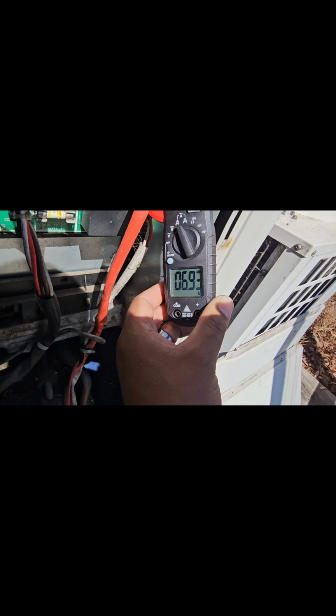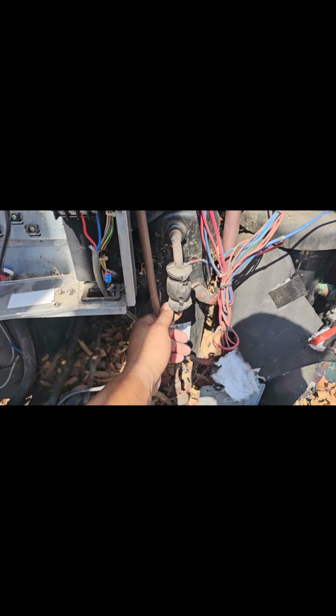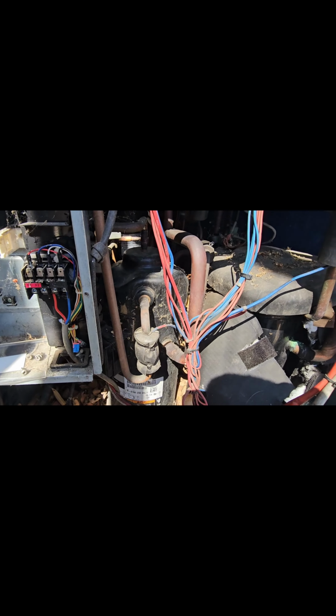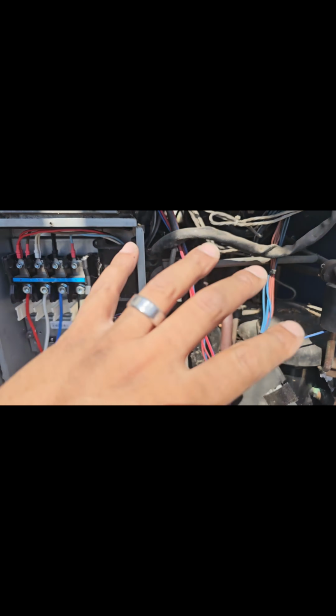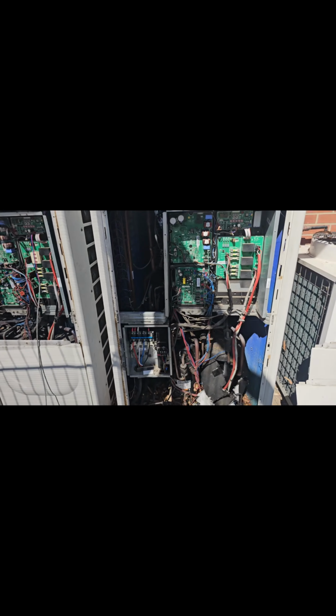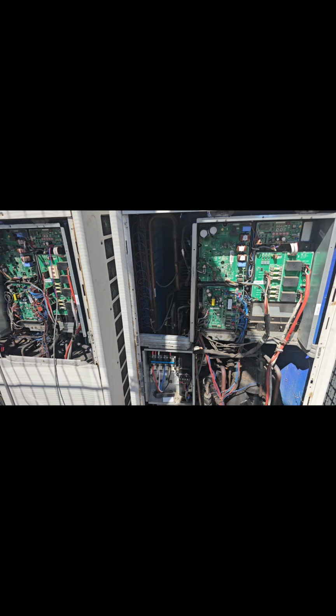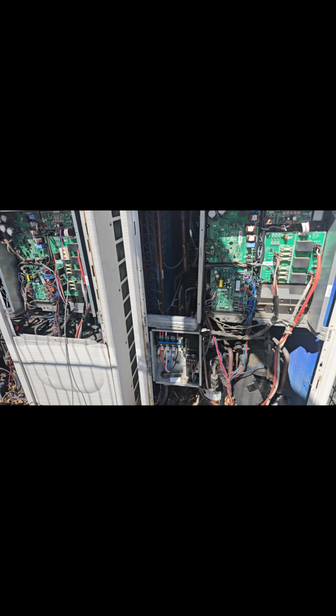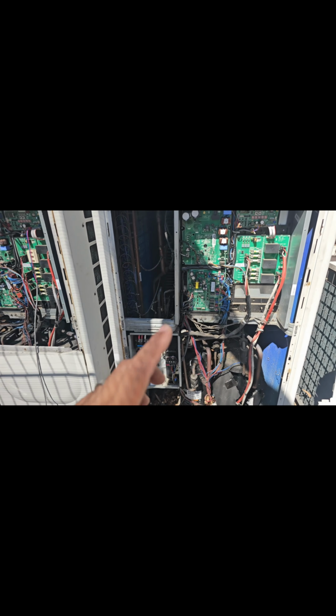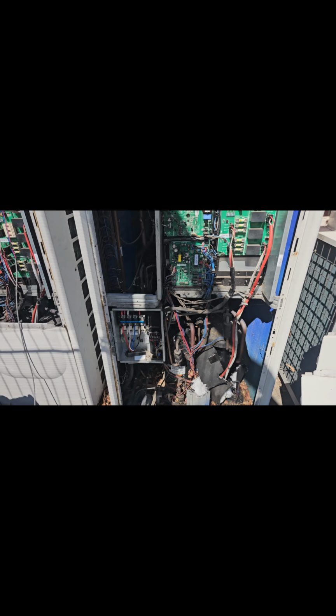The compressor sounds a little rough starting up. Let's just check our startup amps, 6.9. Okay, we're gonna just monitor this guy and see. We're going to check temperatures. We are going to check our system operations. I'm going to have to close some of these panels, simply because you can obviously see there's a tremendous amount of air that's been drawn over here. So we want that air to be drawn across our condenser heat exchanger instead of drawing all this ambient air over here, so that we can get a proper representation of what our system pressure is.